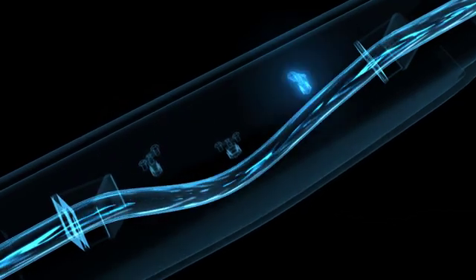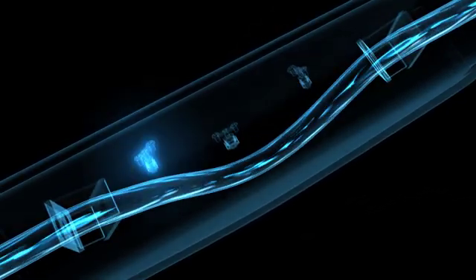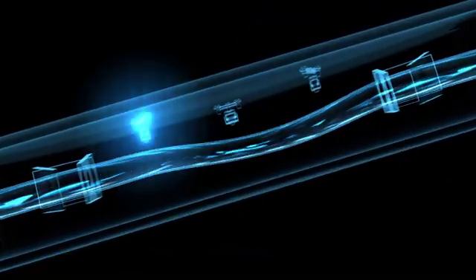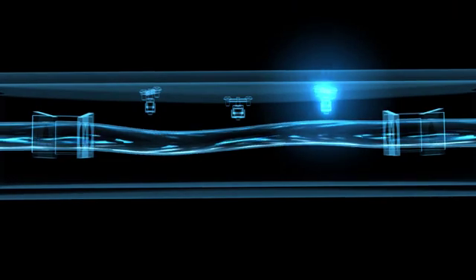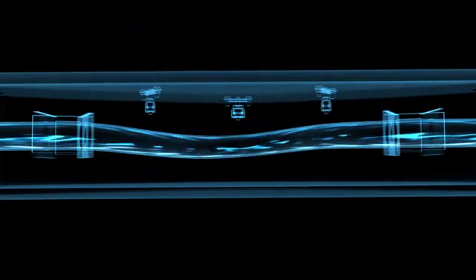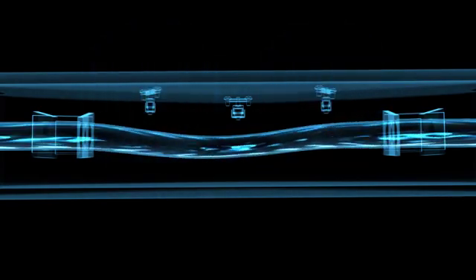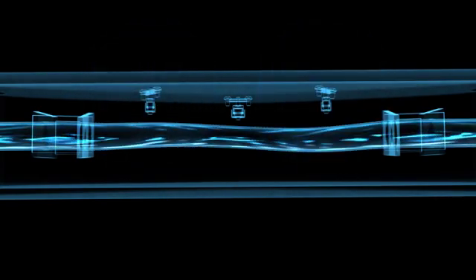As soon as the fluid starts to flow in the measuring tube, however, additional twisting is imposed on the oscillation as a result of the liquid's inertia. Now, due to the Coriolis effect, the inlet and outlet sections of the tube oscillate in different directions at the same time.